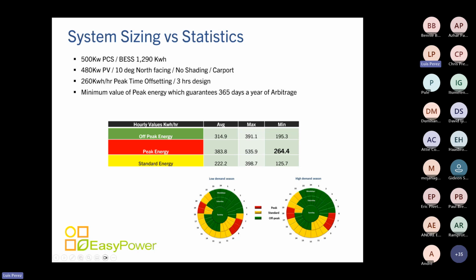So in the case of this system, we do have PV assistance as well, and it's going to become quite important when you see the end results of these simulations. We have assumed that we put 480 kilowatts of PV on a carport, not your typical low efficiency complex type of setup where they mount 10 modules on the top of each residential block, but something built for efficiency. We have a BESS of 1,290 kilowatt hour, designed for 260 kilowatt hour per hour peak time service for 3 hours. So now you understand where the 260 kilowatt comes from, because that's the minimum that we actually saw.